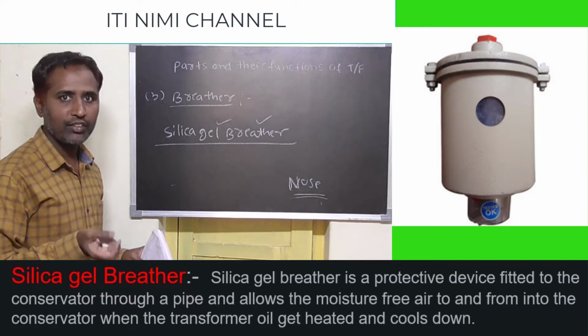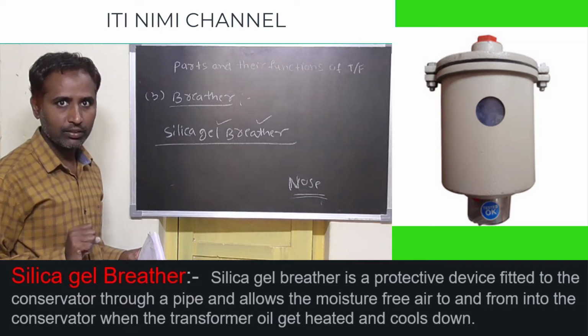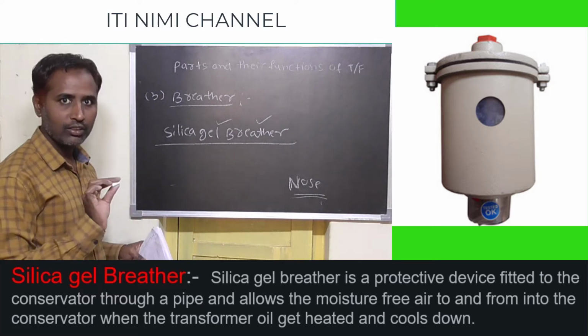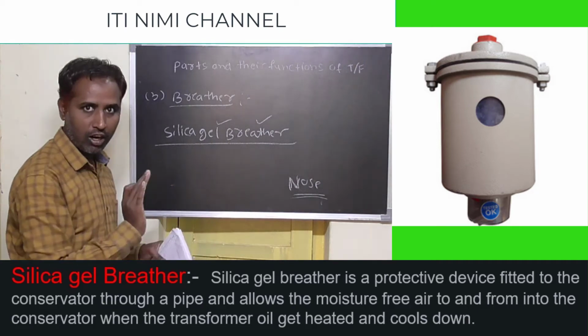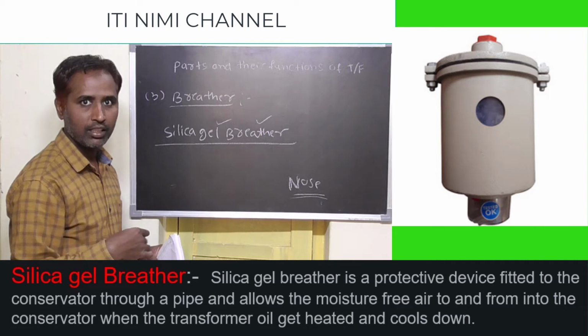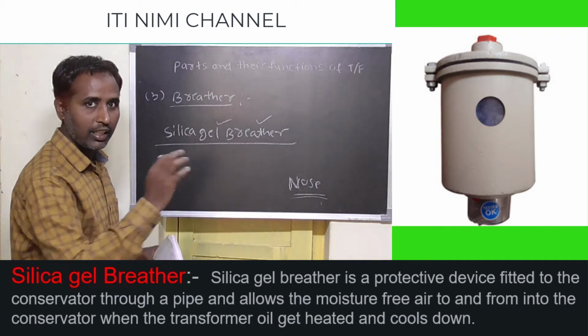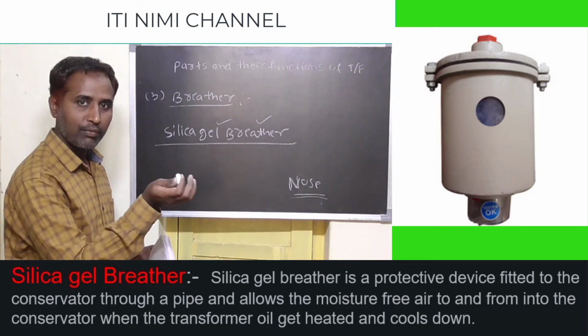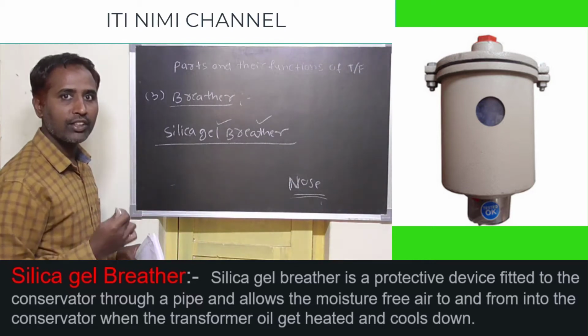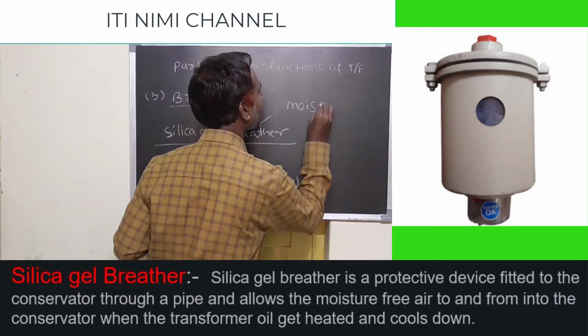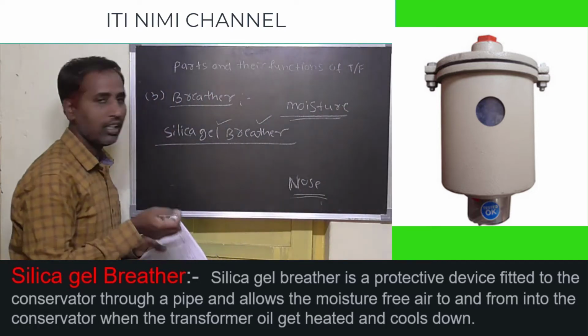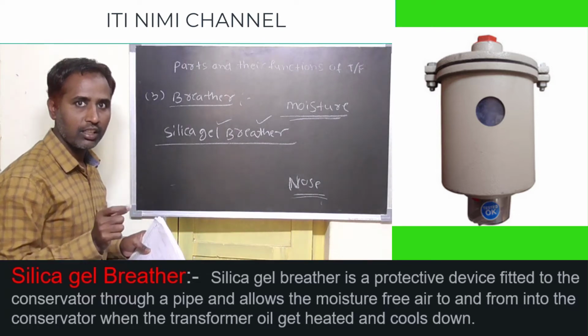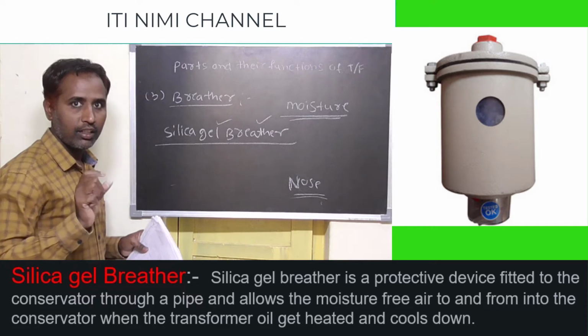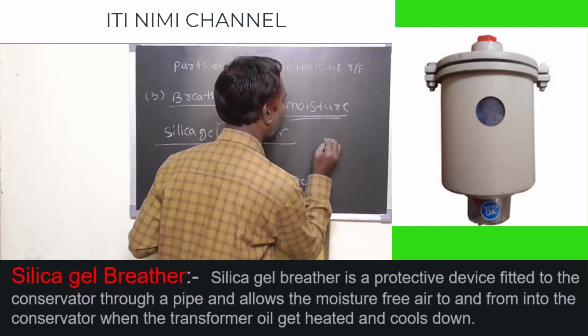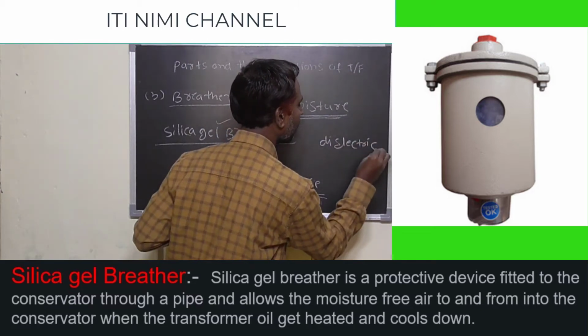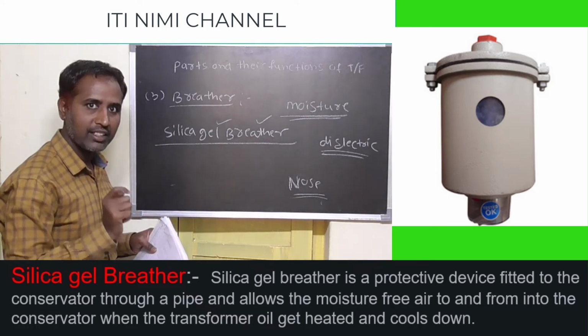What will happen if fresh air comes inside the transformer directly, suppose there is no breather? Just fresh air coming in and hot air going out. While the fresh air comes inside the transformer, it comes along with moisture, and this moisture reduces or deteriorates the dielectric strength of the oil.